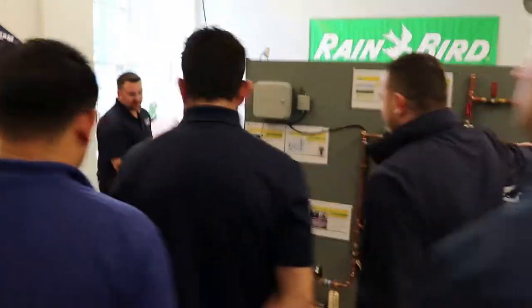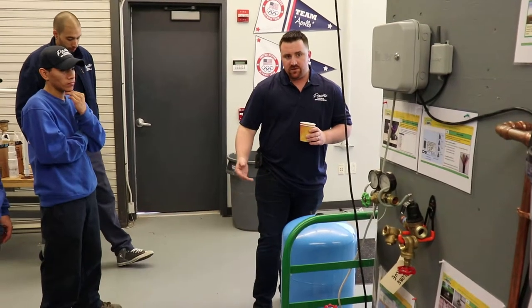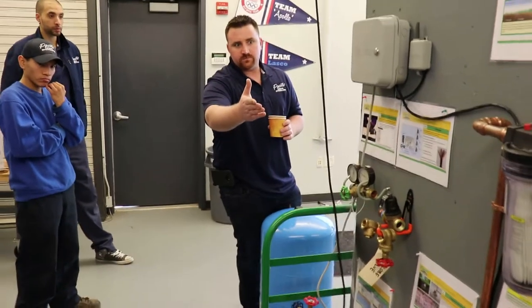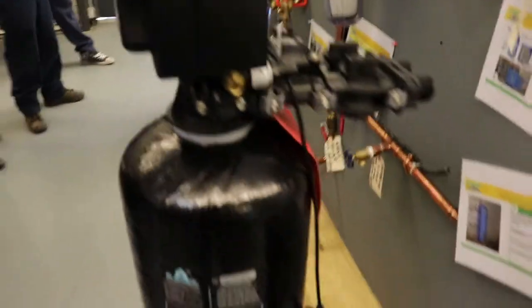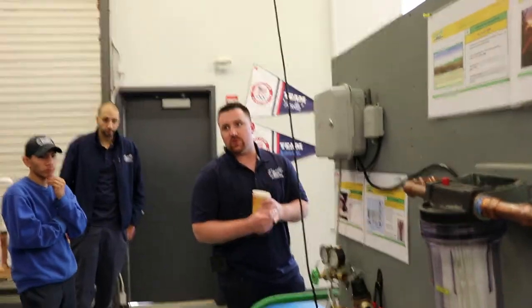What you always want to do — depending on the size of this and the size of the house — is when there's a well system, you usually have a water softener as well. Never cut a sprinkler line in after a water softener. A water softener is usually pressure regulated; it has to be under 50 pounds to work, and it's also a huge restriction of flow.